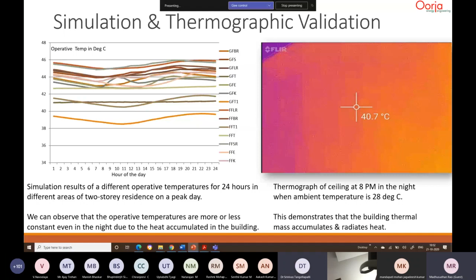When we walk inside our house, it's like an oven. But when we walk outside and are in the balcony, we don't feel the same heat, because the hot surfaces are not radiating heat to us. So what we are saying is, if we can flush the heat from the building itself and not let it come inside - to remove 40 degree centigrade heat, we don't need cold water, we just need water at 25 degrees centigrade. If I have 25 degrees centigrade, I can flush this heat, so I don't need a chiller.